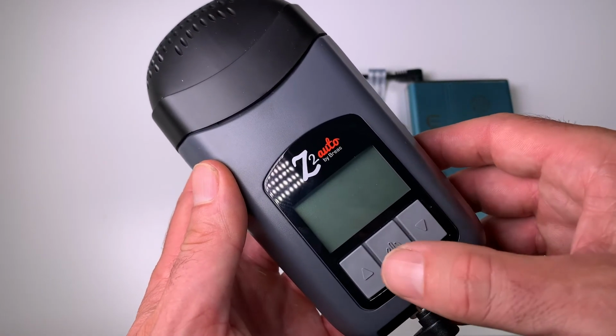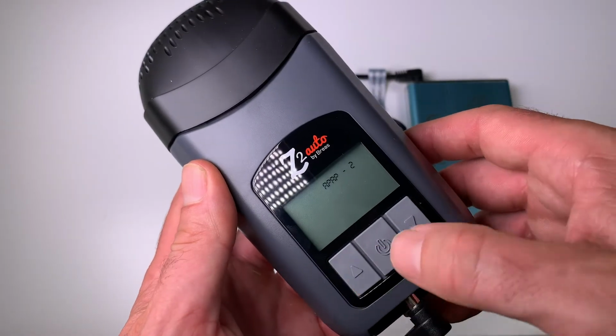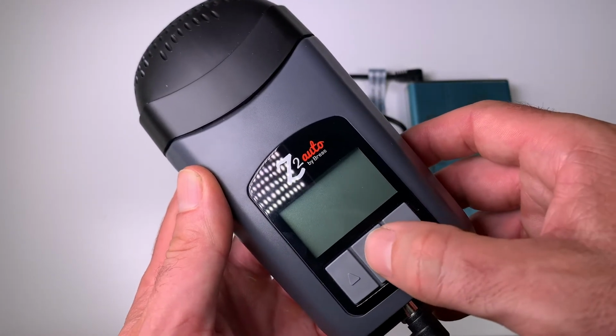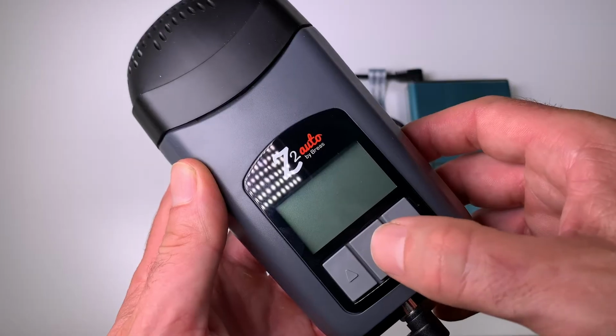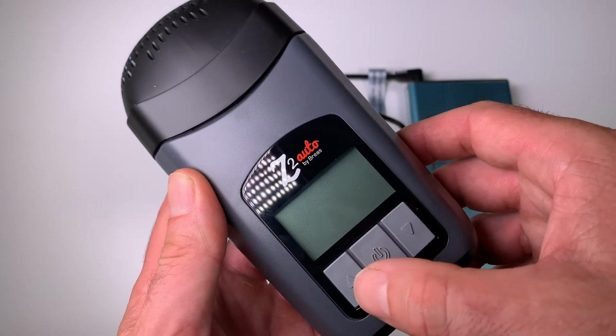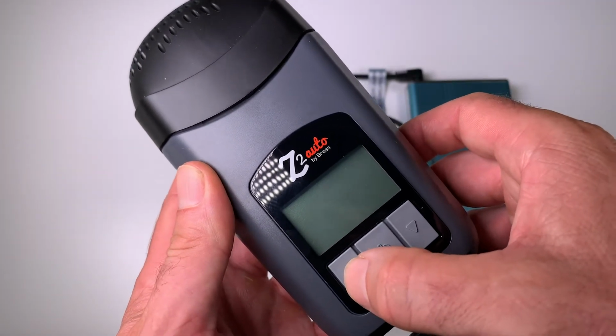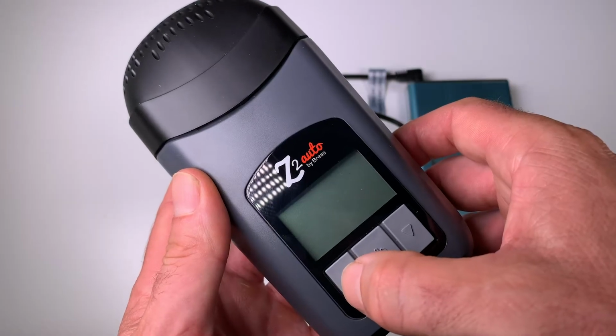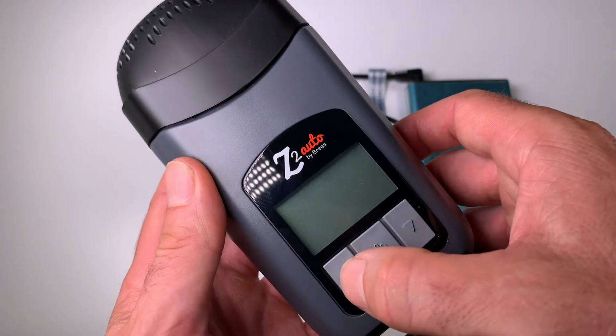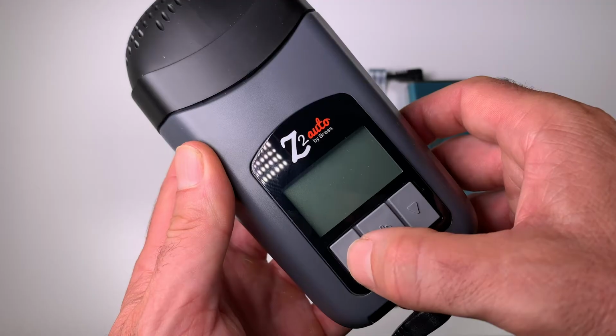Same as always, once we've got to the setting we want, we press and hold the button down to lock it in. But before I do, I want to let you know that if you keep going up - APAP 1, APAP 2 - and press it again, it's going to go into CPAP mode. This is how we access CPAP mode on the device.